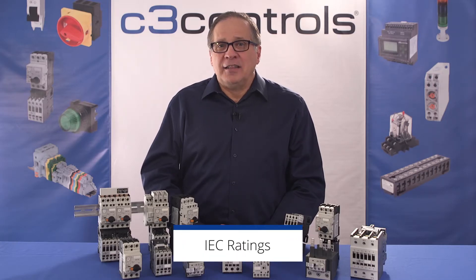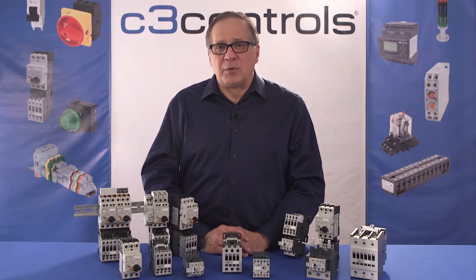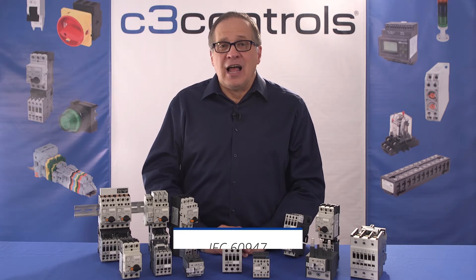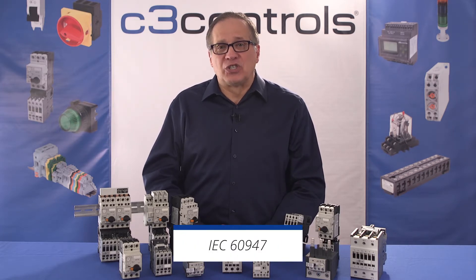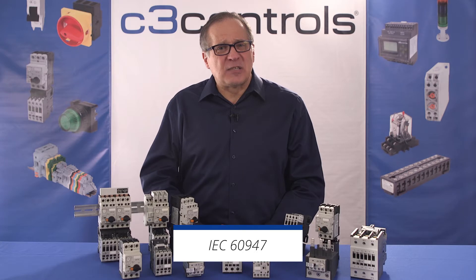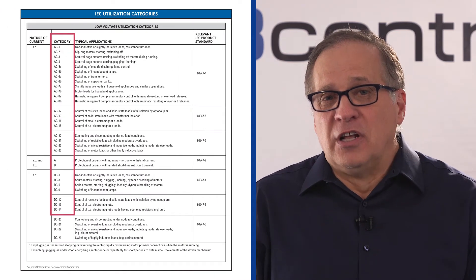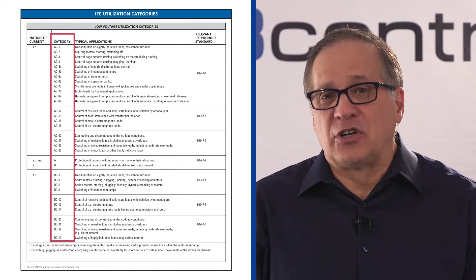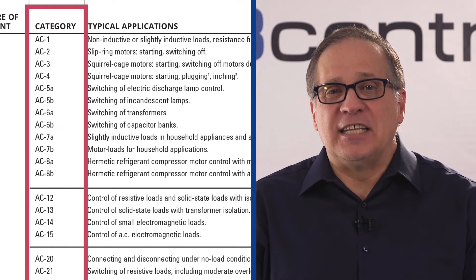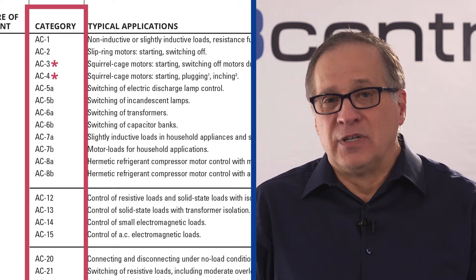Next up is the IEC rating. The International Electro-Technical Commission has specified the operational and performance characteristics for IEC devices in their publication IEC 60947. Standard sizes are not specified by the IEC. The typical duty cycle of an IEC device is defined by utilization categories. For general motor starting applications, AC3 and AC4 are the most common utilization categories. Unlike NEMA sizes, IEC devices are typically rated by their maximum operational current, thermal current, horsepower, and/or kilowatt rating.